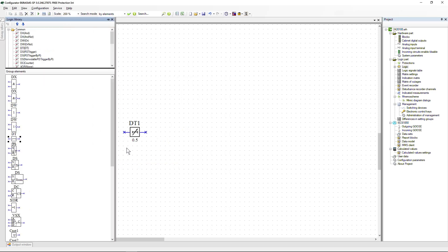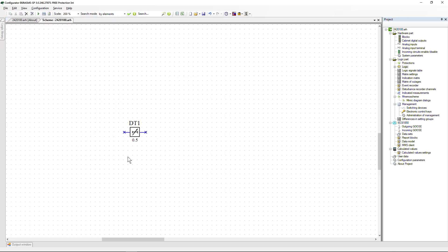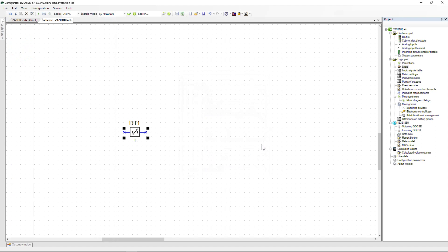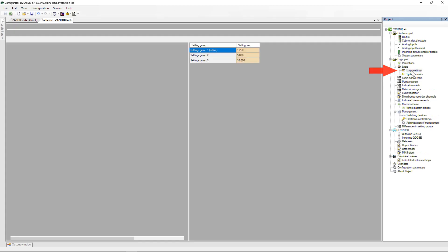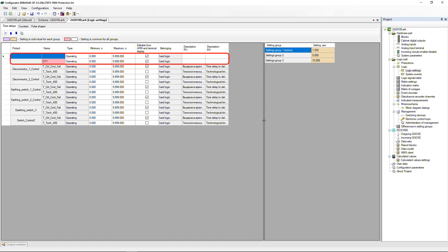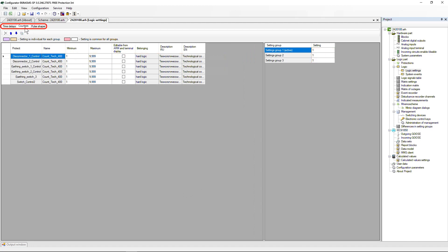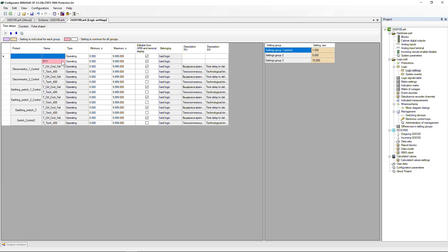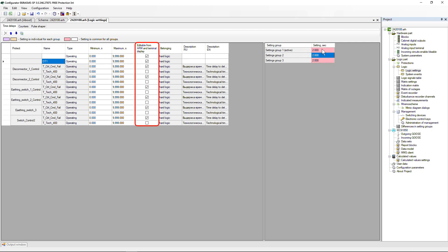Settings of logic elements in the configurator are specified in two ways. The first is to open the properties of the logic element in the logic diagram and specify the setting value. The second way is through the Logic Elements section, where all logic elements with settings are displayed, divided into tabs by element type. Changing settings via the Smart Monitor software and the IED menu is available provided that the logic element is checked in the column Editing via HMI.